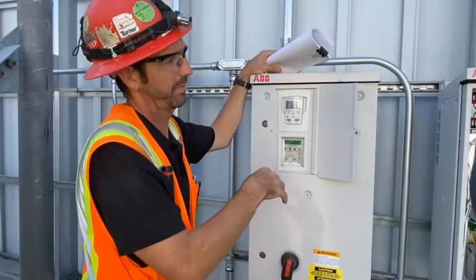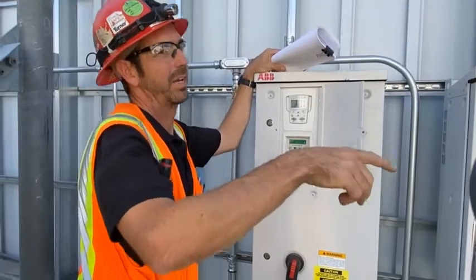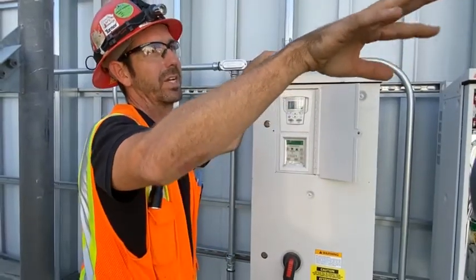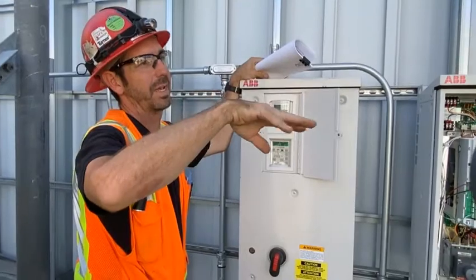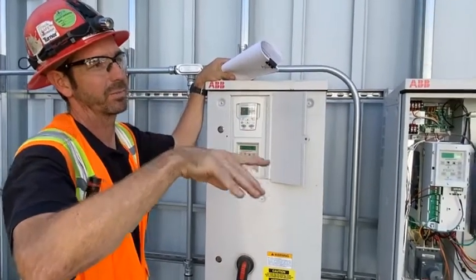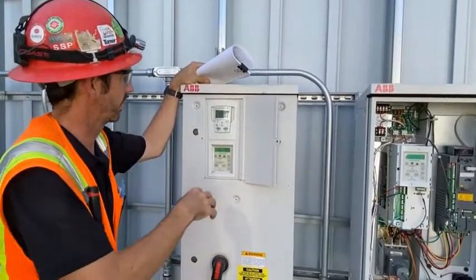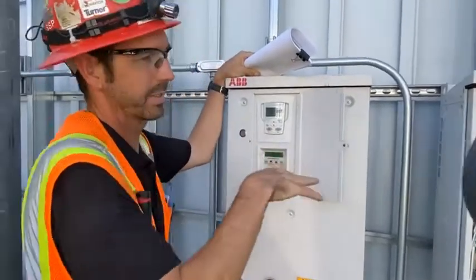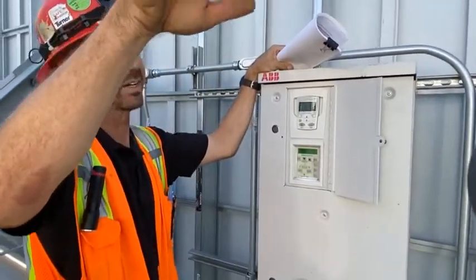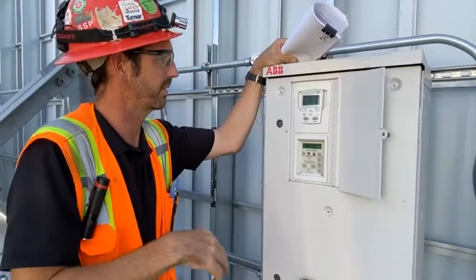What you could do, if you did have to use the bypass, is throttle down the outlet shutoff valve to maintain a certain amount of flow. Build up a little more resistance with the butterfly valves that are here instead of the control valves down in the building.